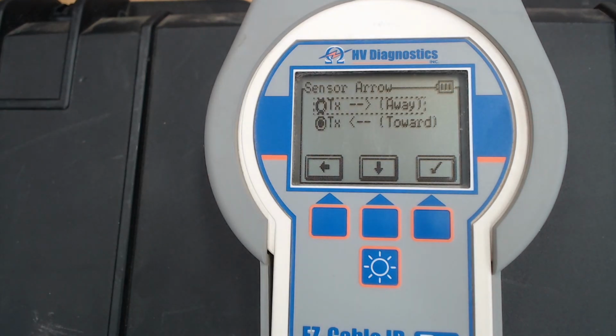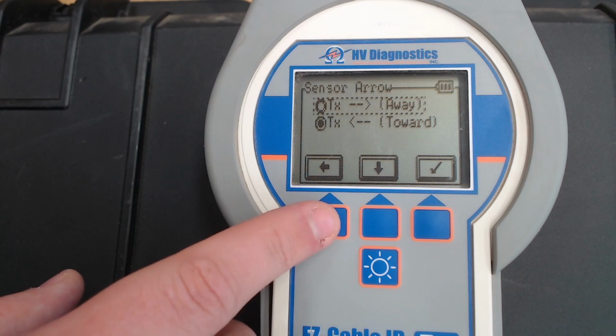We're going to go to sensor arrow. What sensor arrow does is it lets you determine whether you want to face the coil away from the transmitter or towards the transmitter. Some utilities like having all of their units set up to point towards the transmitter, and they won't accept it any other way. Some of them like to have it away from the transmitter and won't accept it any other way. This setting can be set here at the factory before we ship it out to you, or it can be adjusted when you receive it. If you wanted to change it the other way for some reason, that option is available to you. The supervisor can call in, get the code to unlock the handheld unit. They can go in and change that setting, and relock it so it can't be changed by accident in the field the wrong way. So we're going to leave this one towards us.